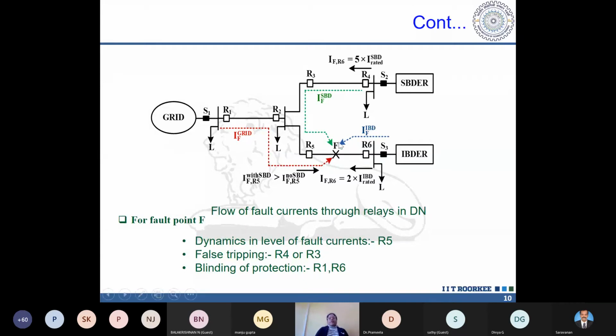For fault point F, the protective device R5 is going to see dynamics in fault current, meaning it will see a change in current magnitude, because this relay sees two fault currents: one fault current IF grid, the red one, and another contribution IF SBD, the green one. These two are in the same direction. In general, when two current phasors are in the same direction they are added, and when in opposite directions they are subtracted.